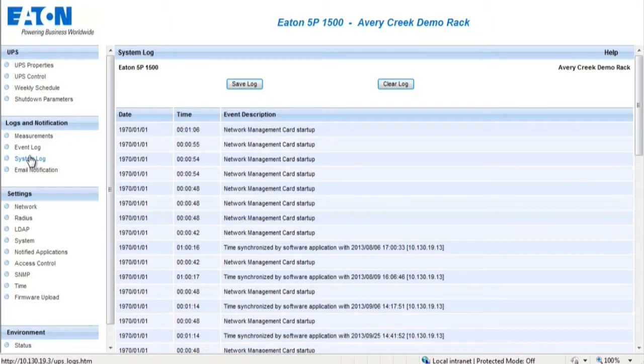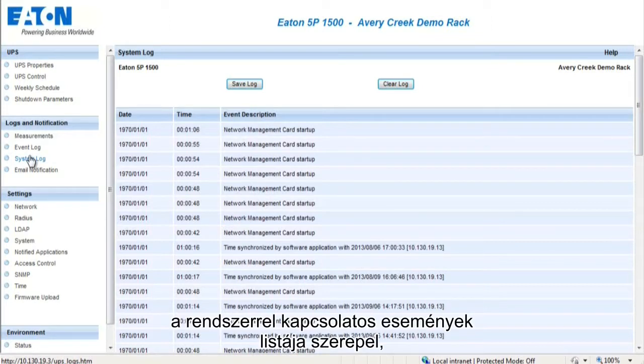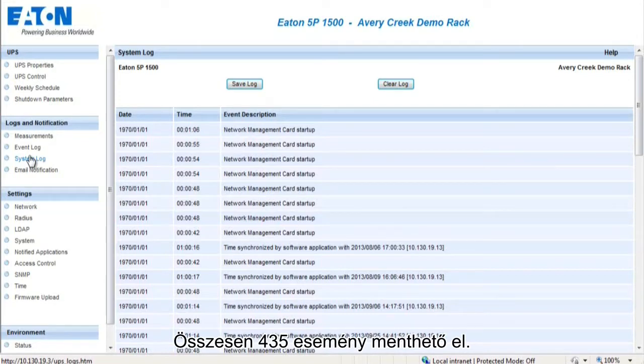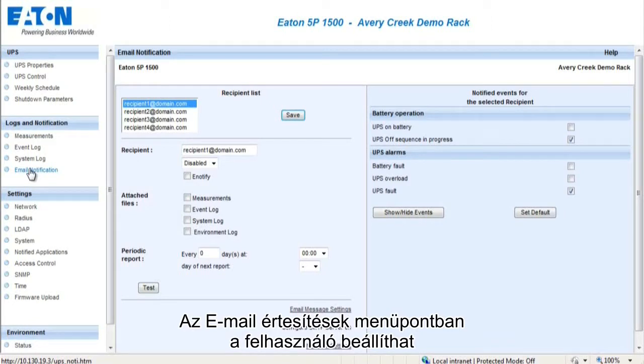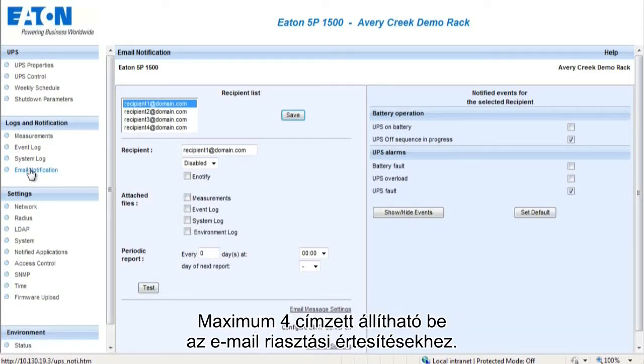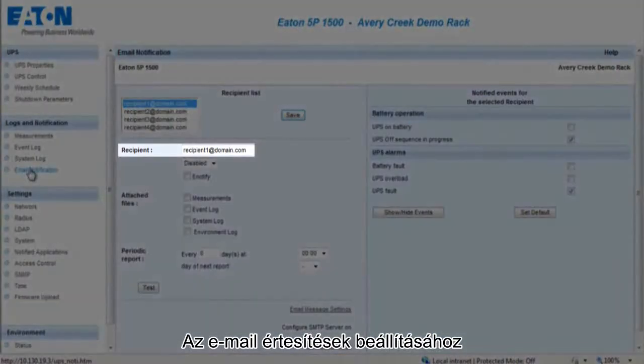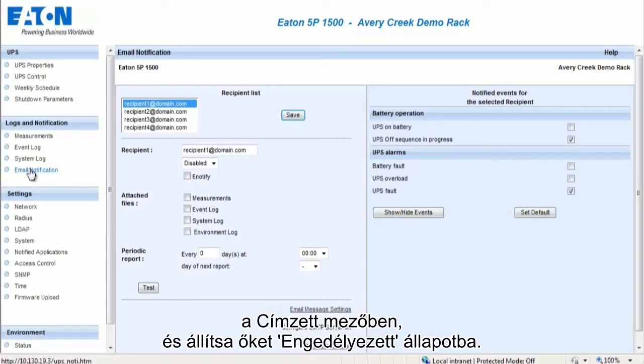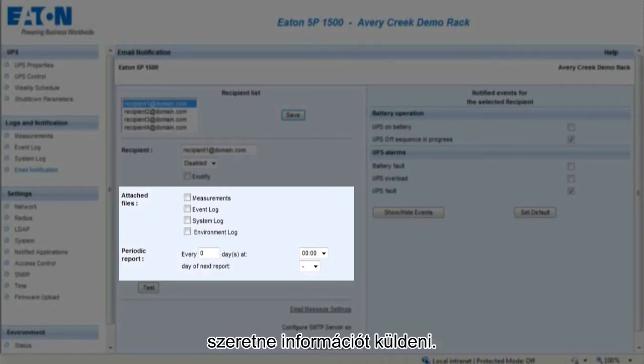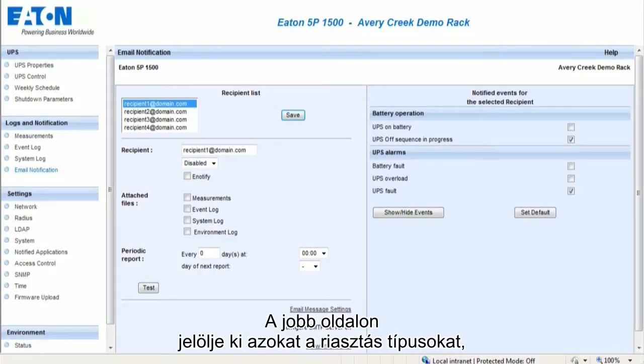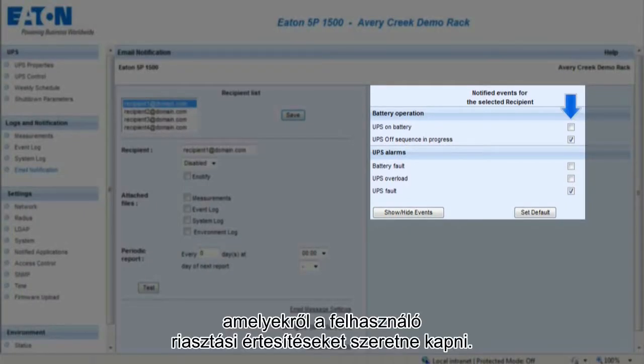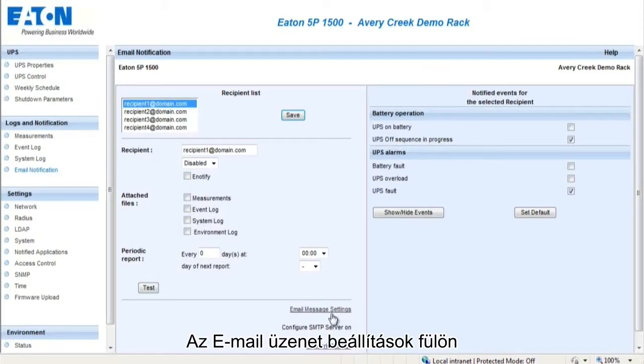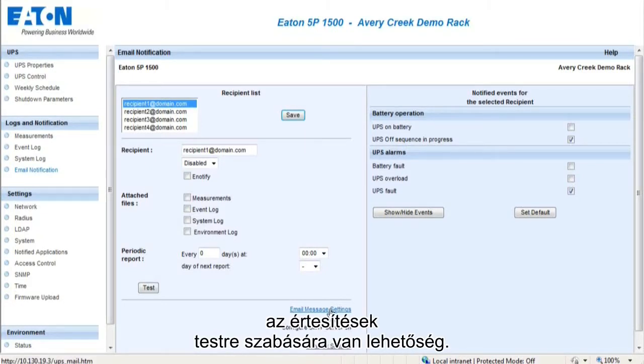The System Logs section provides a record of the system-specific events experienced by the UPS. A total of 435 events can be saved. The Email Notifications section enables the user to set up an email or SMS alert source. Up to 4 recipients can receive email alert notifications. In order to set up the email notifications, enter the recipient's email address in the recipient field and change to Enabled. Select the types of files and determine how often the information will be sent. Save the selection. On the right-hand side, select the types of alarms for which the user would like alert notifications to be sent. The Email Message Settings tab allows the notifications to be customized.